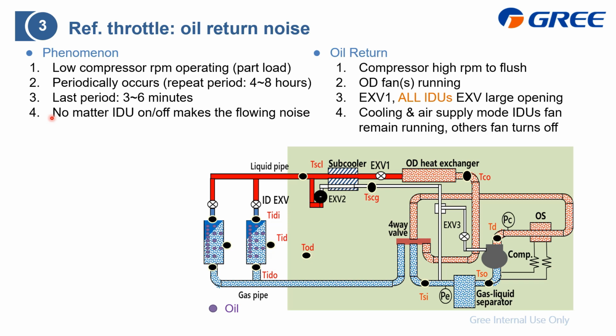As you know, for the VRF, especially in part load condition, the oil will also be output from the compressor, which on this diagram we output the oil from here, and this is in cooling. Then it goes to the outdoor heat exchanger, and then to the indoor unit, and the oil and refrigerant mixture makes heat exchange here, and the refrigerant will become gas and flow back to the outdoor unit. It's okay, but the oil still remains at the indoor unit heat exchanger, which is at this part. The purple is the oil. And the target of the oil return is to make this oil flow back to the outdoor unit, to here, the gas liquid separator.